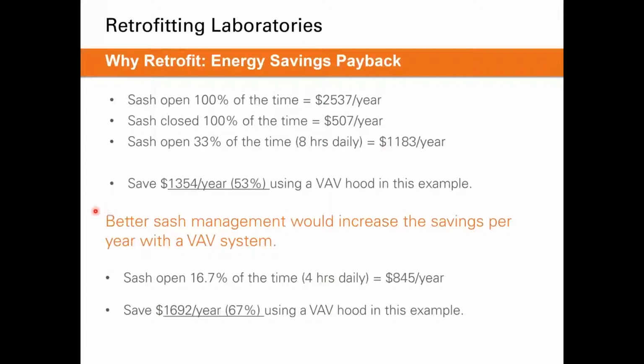And I mentioned it before, but I want to mention it again, that better sash management would increase the savings per year with the VAV system. So if we cut this number in half, so rather than the sash being open 8 hours every day of the year, it's open 4 hours every day of the year. So better sash management in this case, when the hood is not being used, drives the operational cost down further to $845 per year.